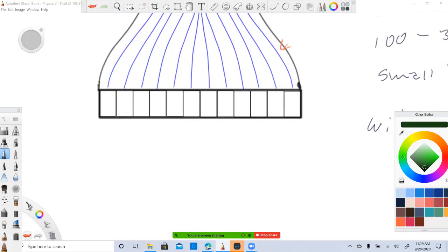So when we talk about the width. Yes, I did. The width of one element is here. So that's, in this particular type, 1/4 to 1/2 of a wavelength. Now remember, that's not thickness. Thickness determines frequency. Thickness, width, yes. Here, let's get rid of some of those, so that's not in my way later on. All right, 1/4, 1/2 of the sound's wavelength.